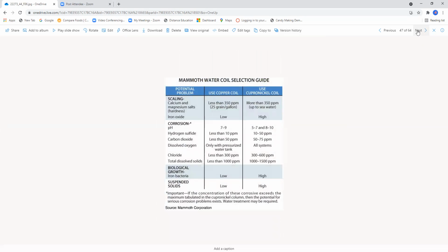Okay, Mammoth water coil selection guide. This is the problem with utilizing an earth loop, utilizing H2O as a water source to remove heat. One of the issues we have to face with this type of equipment is biological growth and scaling, and we have to have treatment options available in order to keep these systems functional. If anybody believes you can circulate water forever and ever without inducing some problems, you've got some issues. By the way, this is found on page 1329.